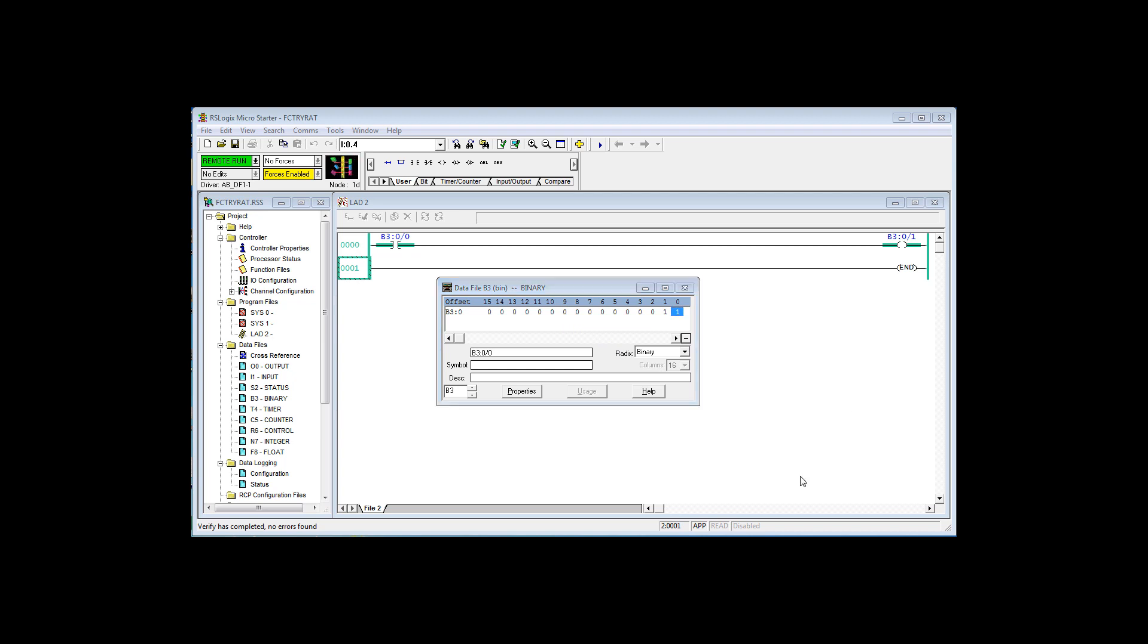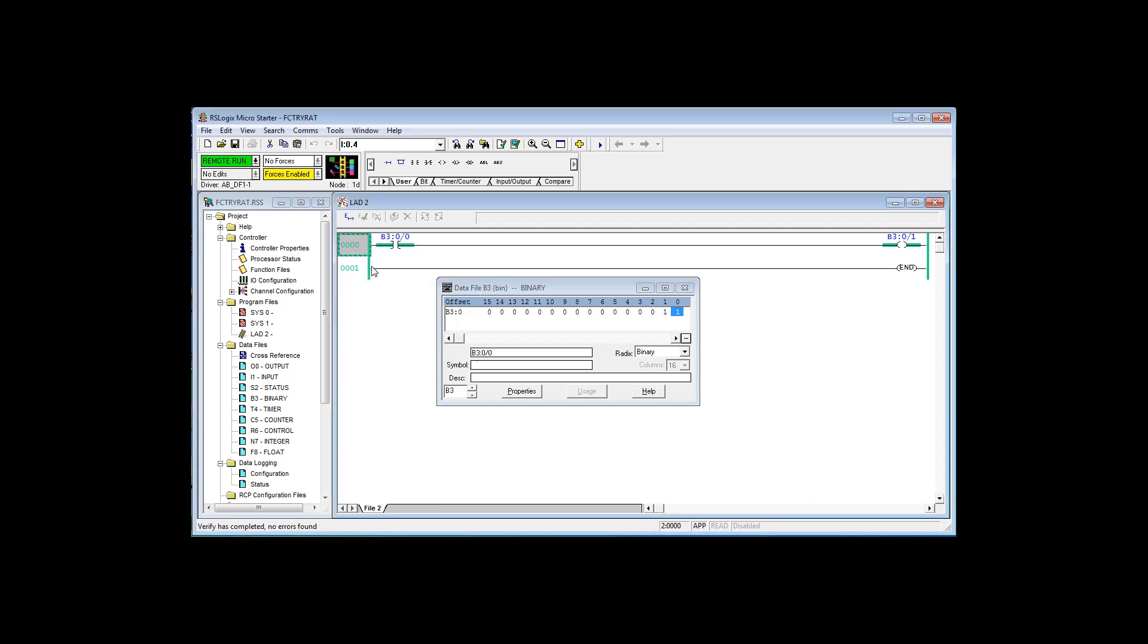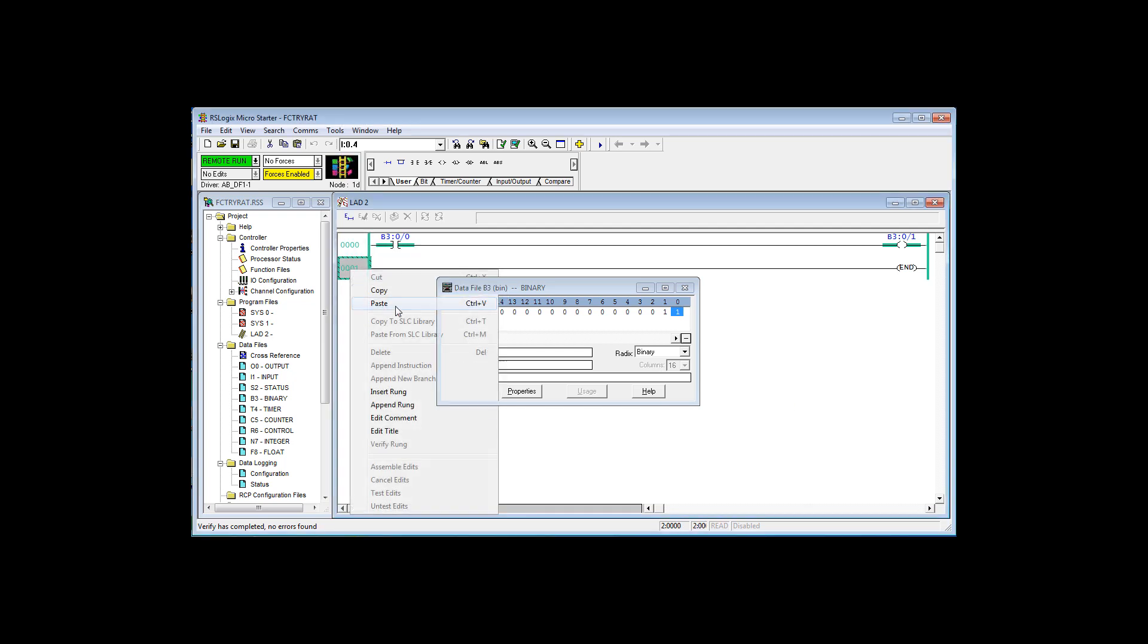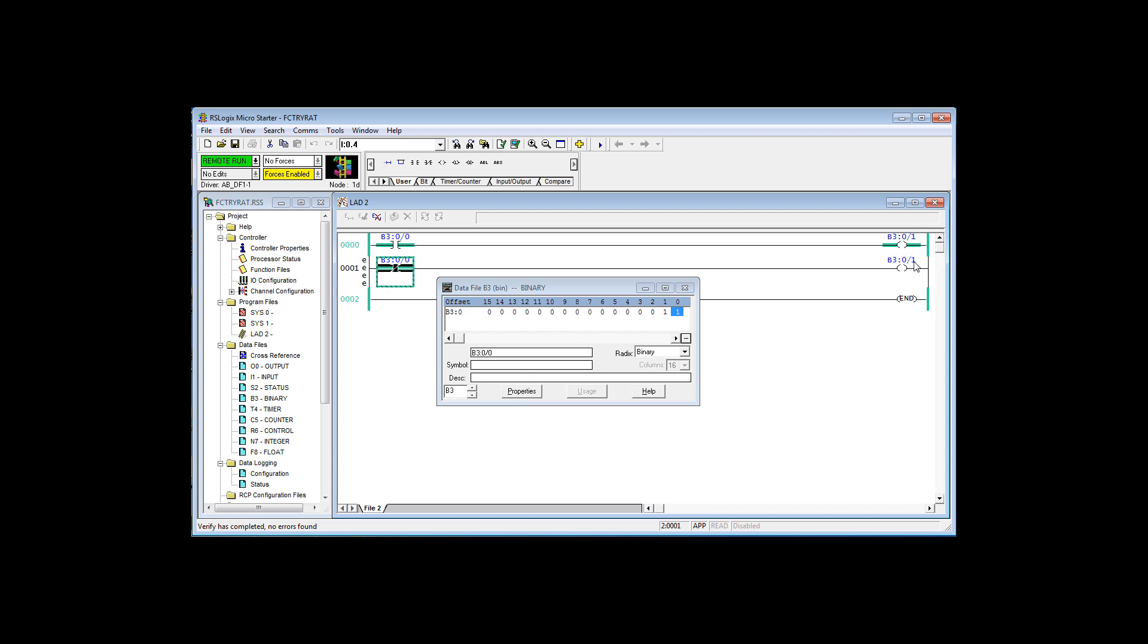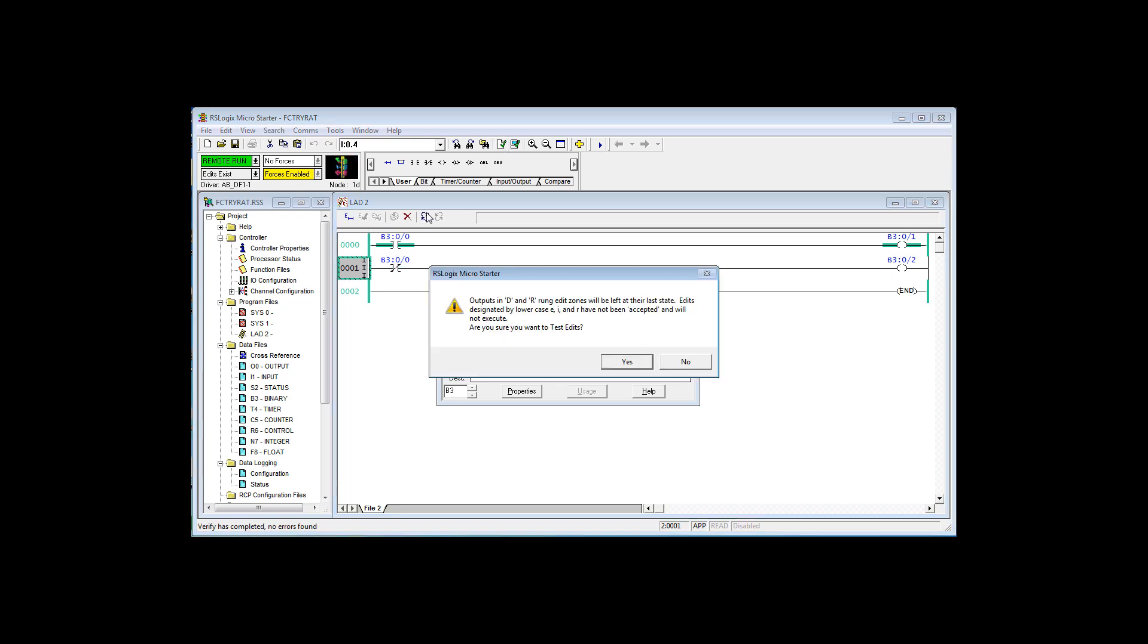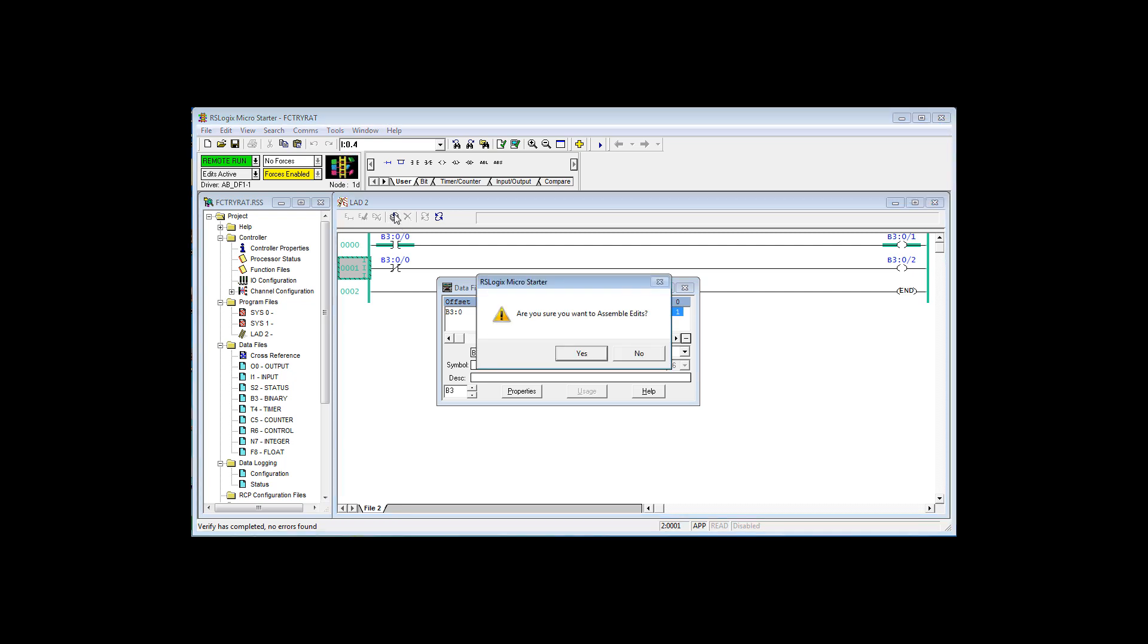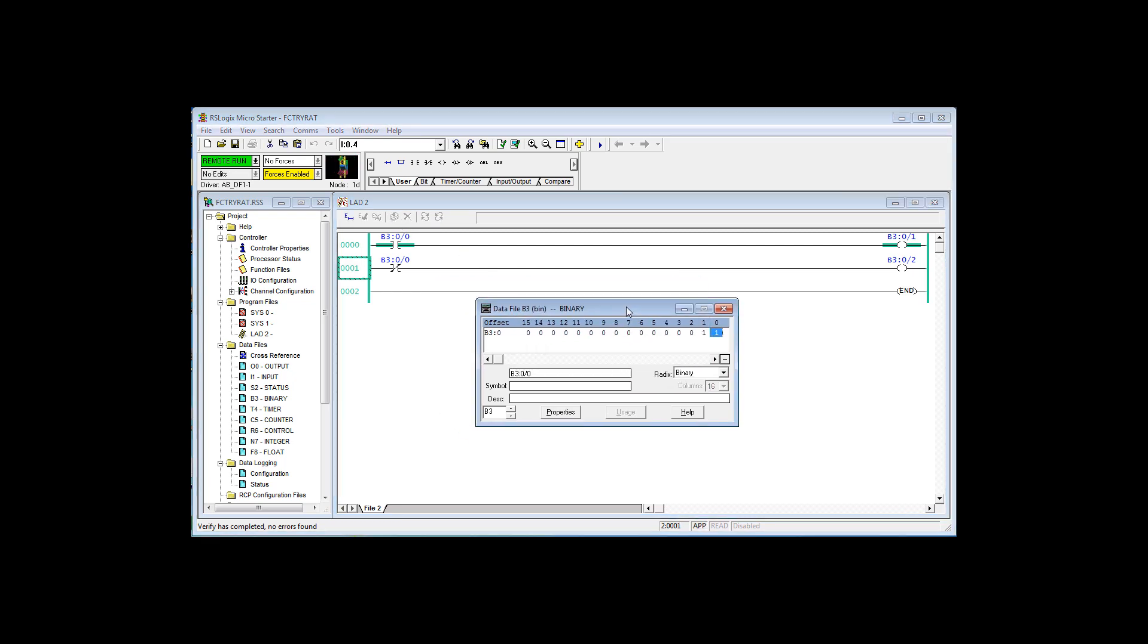Let's add one more rung of logic. I'm going to cheat a bit. Right click, copy, right click, paste. Just like with the word processor. I'm going to change this instruction. I changed it to a true if off, and I'm going to pick a different memory bit to control. Verify, test, assemble. Now notice I did that all online.